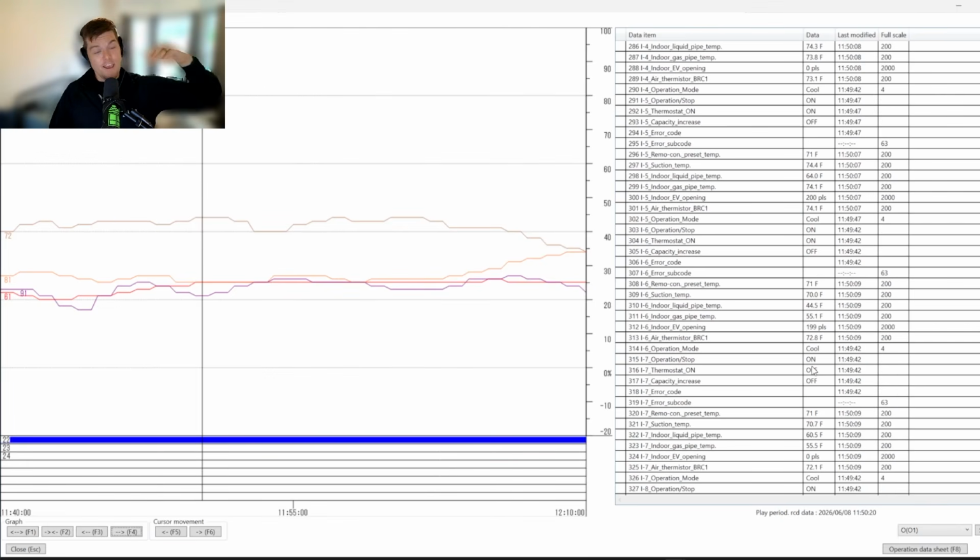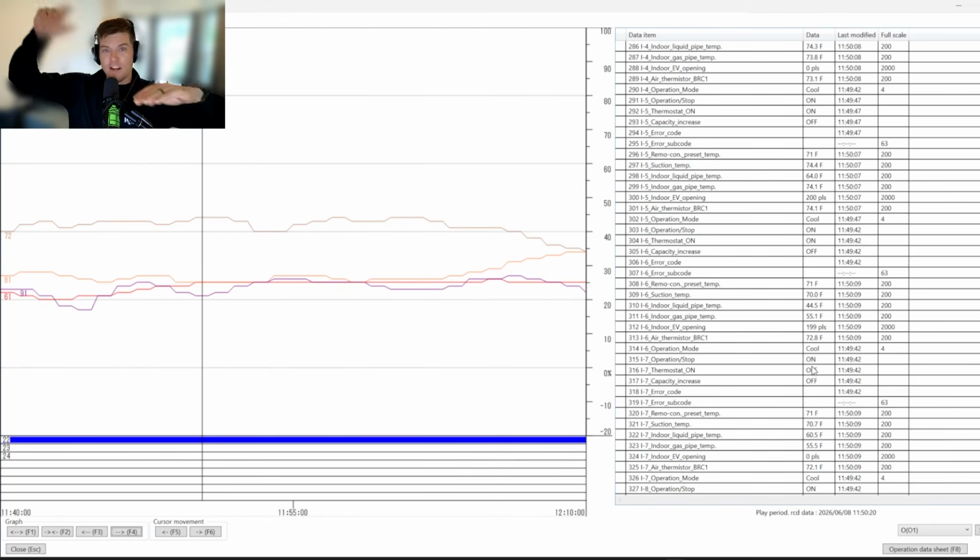If you lower the saturation temperature and drive your compressors to, let's say, 40 degrees, and then you turn around and raise it back up to 50 after the compressors get running and the refrigerant gets flowing and it starts going through the indoor units, what do you think is going to happen when you raise that saturation pressure and saturation temperature on the outdoor unit? Well, the compressors are going to do what? They're going to slow down. And when they slow down, the refrigerant's still moving. We're still getting some low temperature refrigerant and liquid back on the suction line. Because we've changed the saturation, now we start to flood back, which is what you see here.